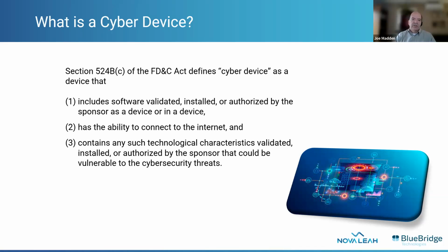They've used an example at a recent conference where they said a manufacturer had a USB port that they disabled, and they used that to upload any new firmware into the device, but they said it wasn't really connected because they've disabled it. Well, FDA responded back by saying, hey, look, there is the foreseeable ability for that device to connect through that USB port. And it was actually kind of funny. There was a tester on the panel with FDA, and they said, show me a disabled USB port and I'll show you access to your device. So the FDA really is trying to make sure that you're addressing not only the devices that are connected, but the devices that have the foreseeable ability to be connected.